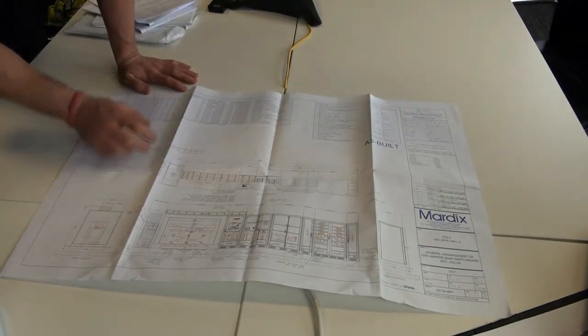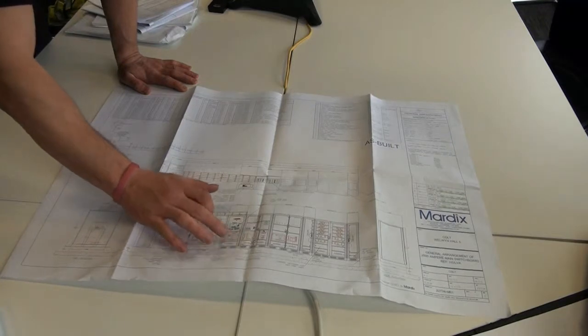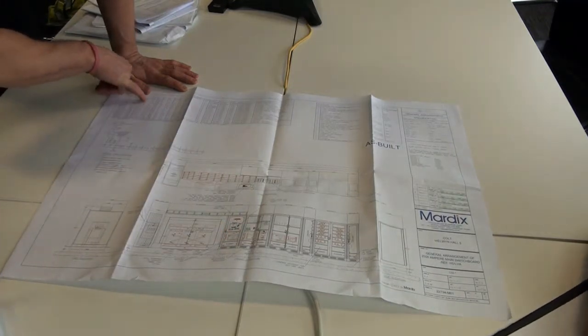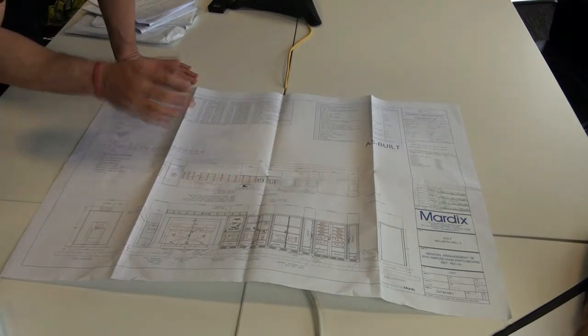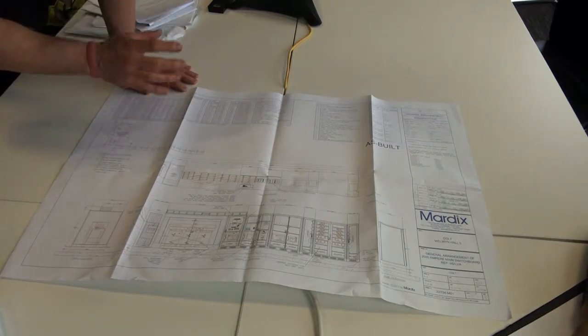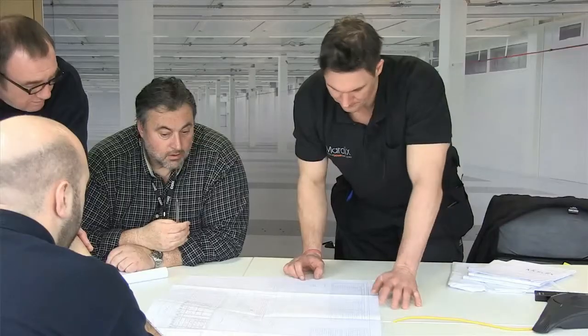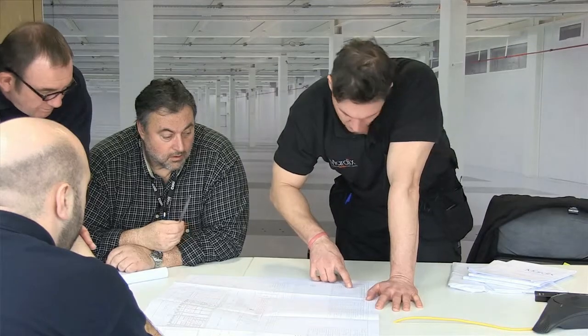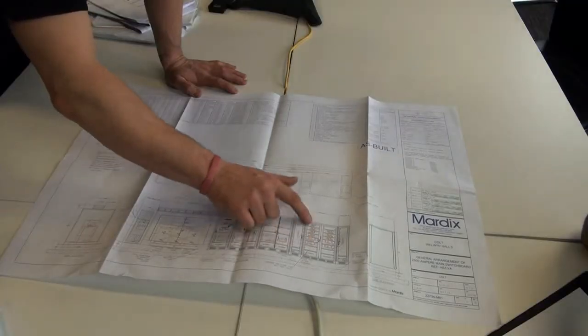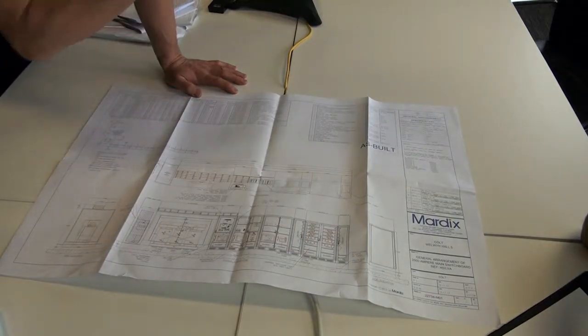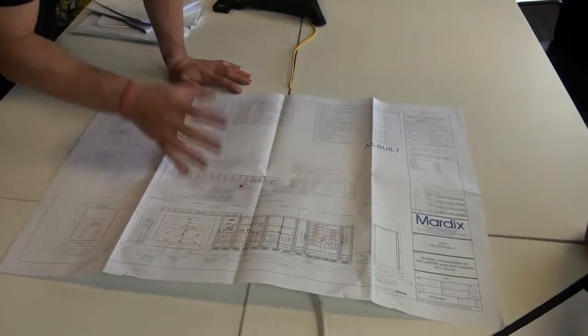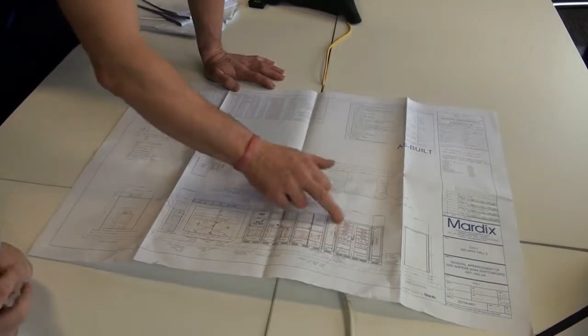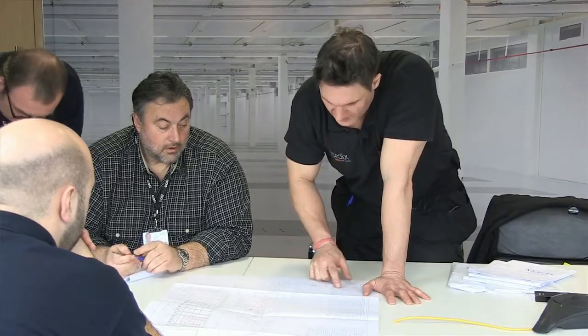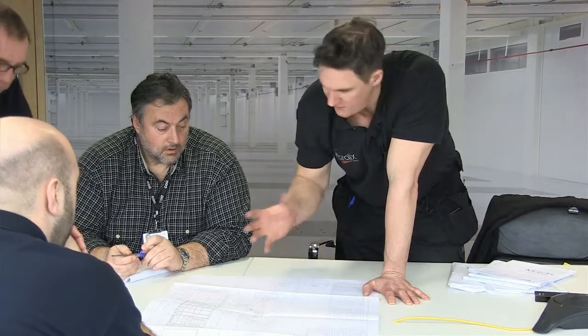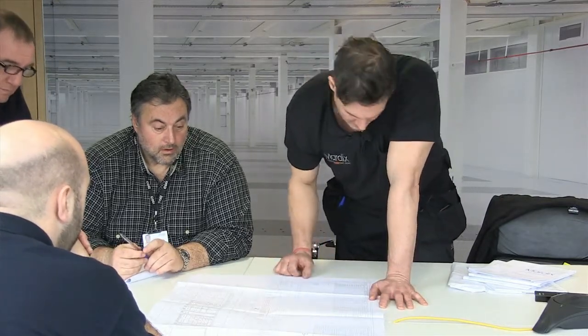Micrologic 5.0E, that is the trip unit. That's a little Micrologic trip unit that sits inside the breaker. Now there's a difference between a 5E and a 5A. One is an ammeter, one is an energy meter. The 5E just gives you a little bit more information in terms of network access and stuff like that. The Micrologic 5.2Es you will find in these breakers here. I don't know if you've ever opened them up and seen one. It's like a little digital display which goes onto a Modbus ring. The Modbus ring goes onto the HMI, and you can access all of the information. So it's kind of like a meter, but sits within the breaker. That's kind of what the E stands for, an energy meter. It gives you all of those values. It saves you putting a meter in, and they cost a lot more money, obviously.